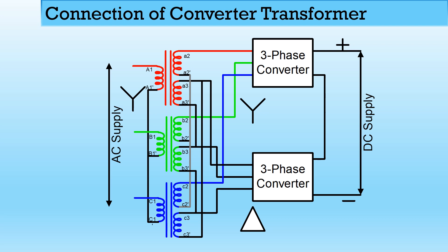A2 dash, B2 dash, and C2 dash are connected together to form a star connection. From A2, B2, and C2, one output is taken and connected to a three-phase converter — so the second winding (suffix 2) forms a star connection. The third winding (suffix 3) is connected in delta: A3 dash is connected to B3, B3 dash is connected to C3, and C3 dash is connected to A3. Output is taken from A3, B3, and C3 and fed to a second three-phase converter. The advantage of the delta connection is that zero sequence current is trapped, so triplen harmonics are automatically reduced to zero.